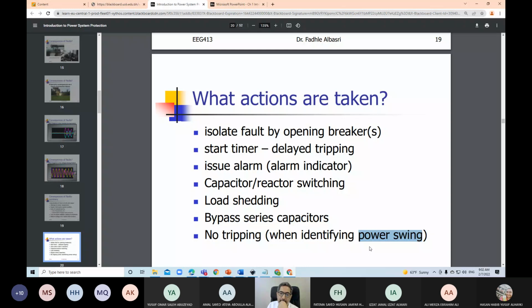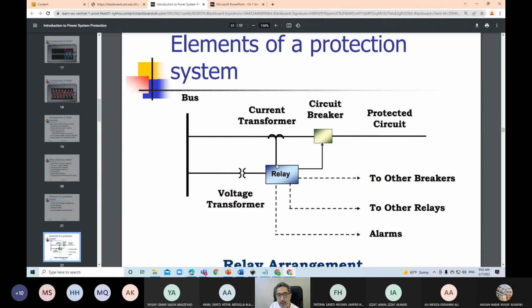That's why we need a current transformer and a voltage transformer as inputs that step down the high current to a lower current, to a standard value, and the voltage transformer will reduce the voltage to a lower, standard voltage. Normally the voltage here could be 400 kV, but this is 110 to 120 volt at rated voltage. Similarly, this could be 1000 ampere, the rated current of the line. We reduce it from 1000 to 5 or 1 ampere here. So these are the current and voltage transformers.